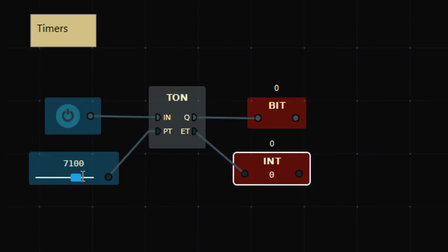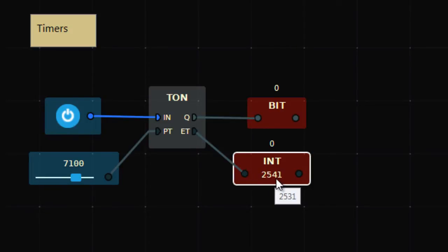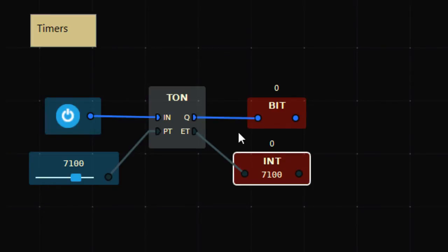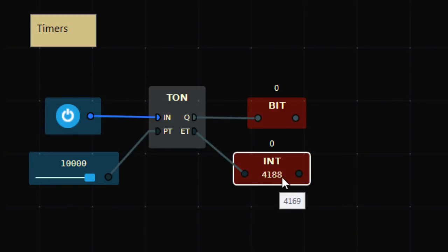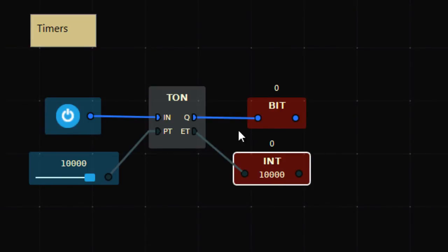Let me increase the delay to 7100 milliseconds — 7.1 seconds. When I press this switch, the timer is enabled and it starts noting the time. After 7100 milliseconds, the output turns ON. I can also change the delay to 10 seconds; at 10 seconds this bit will be ON. That's how you provide a delay using the T-ON timer.